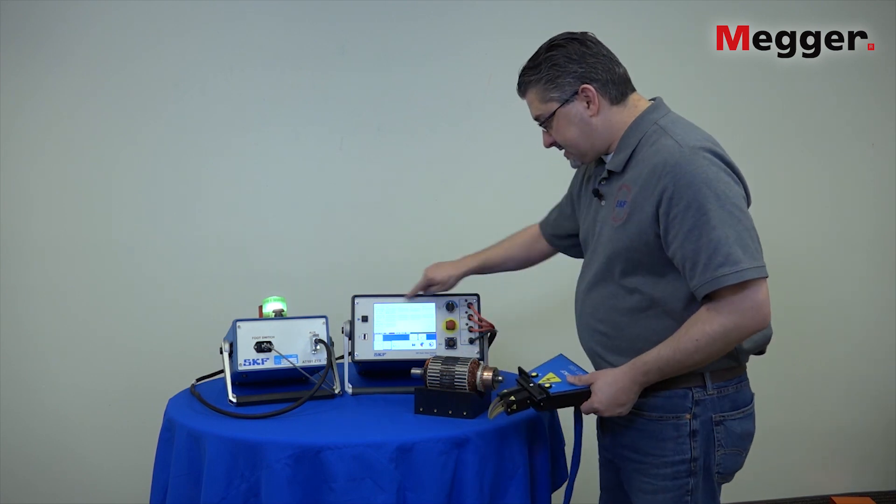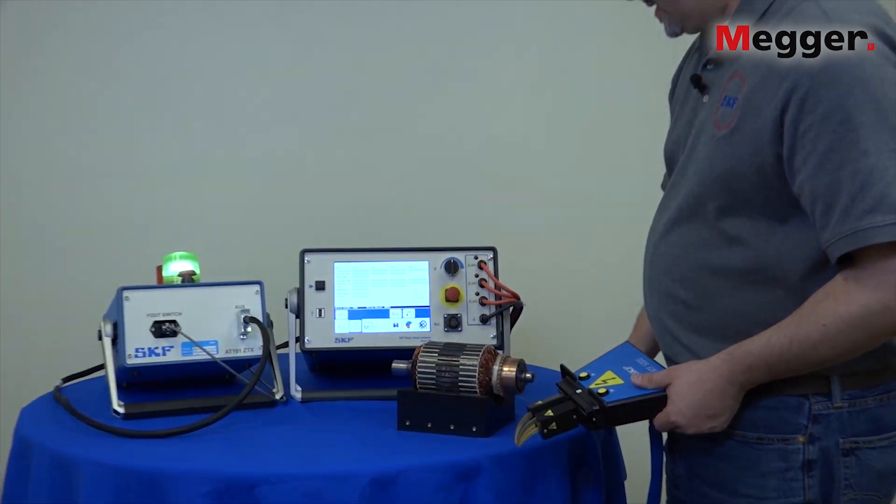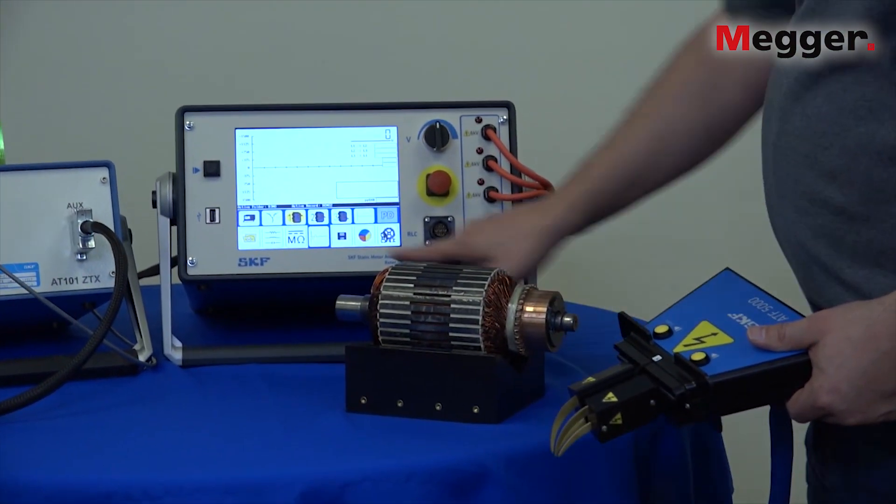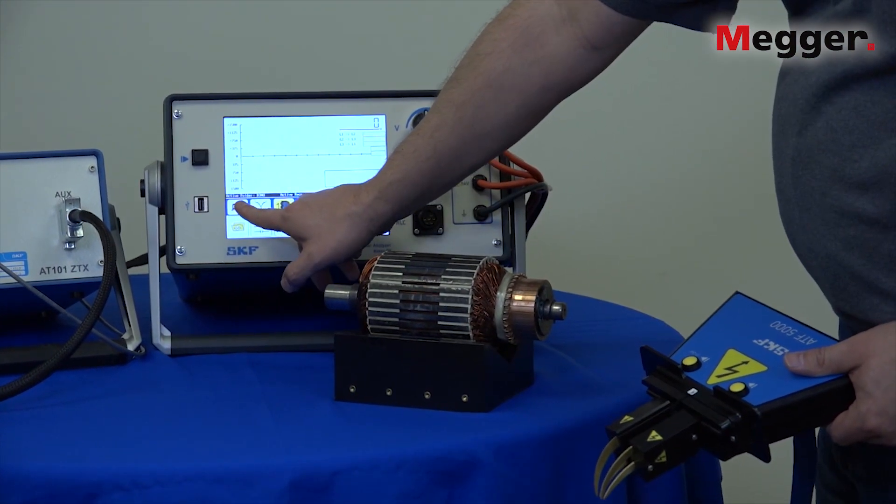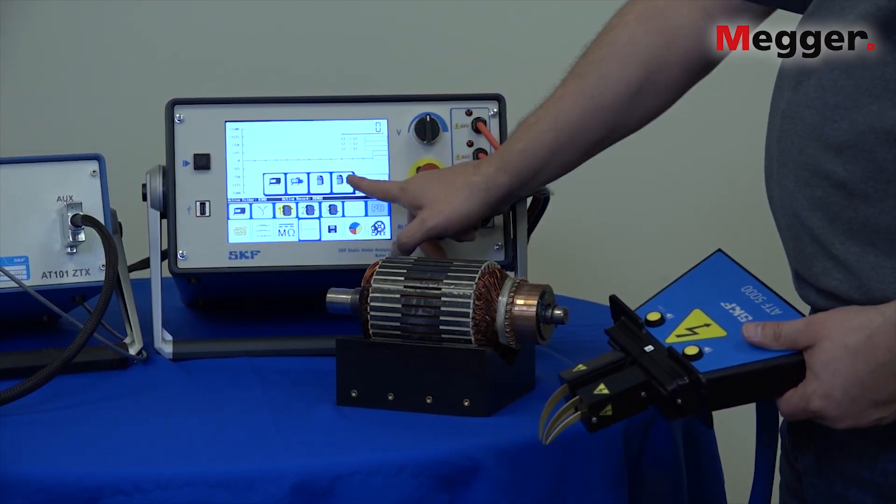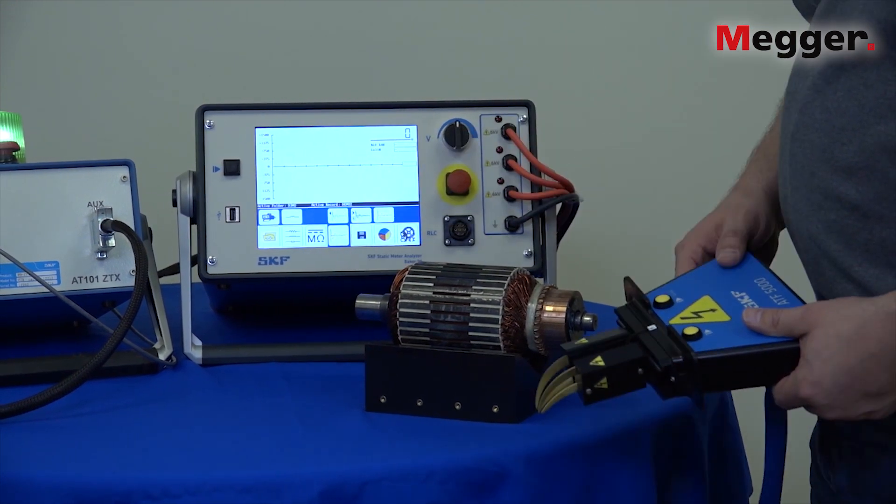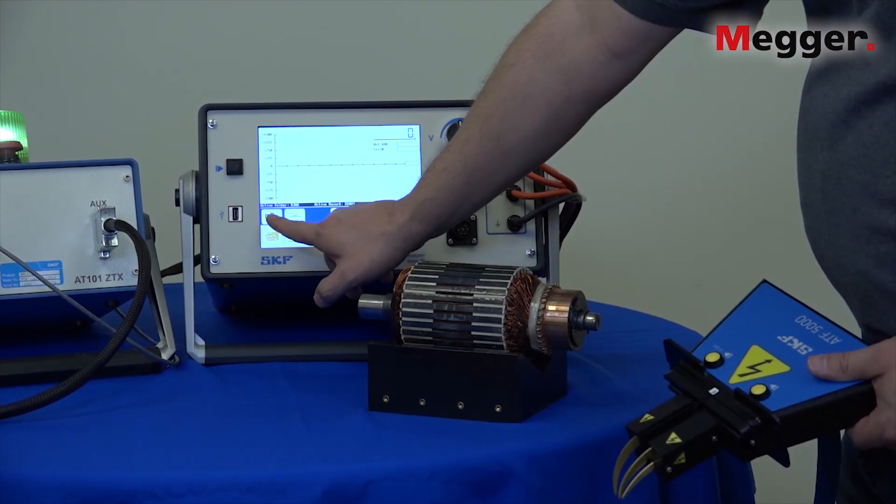On the DX screen we want to select the icon for surge testing, and now under the device we want to make sure we select the ZTX. Again, if you're doing armature testing with the power pack you can select the power pack as your option. We'll select the ZTX and we'll see the icon displayed down here.